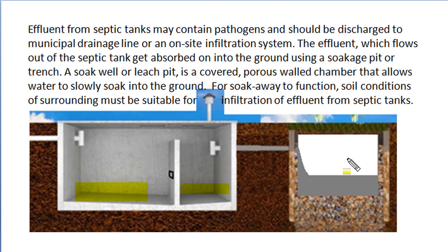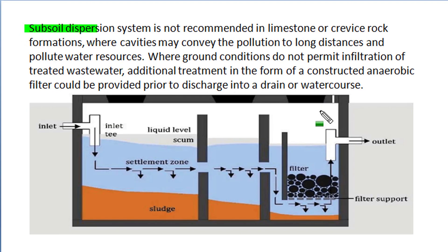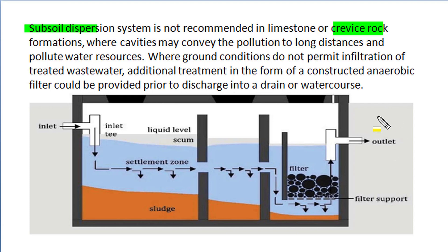The effluent which flows out of the septic tank gets absorbed into the ground using a soak pit or trench. This soak pit or leaching pit is a covered porous-wall chamber that allows water to slowly soak into the ground. For a good soak away to function, the soil conditions of the surrounding area must be suitable for infiltration of effluent from the septic tank. Subsoil dispersion or infiltration of effluent is not recommended in soil conditions which have limestone or cavernous rock formation, as the liquid effluent may create cavities that convey pollution over long distances and may pollute drinking water resources. Where ground conditions do not permit infiltration, additional treatment in the form of a constructed anaerobic filter could be provided prior to discharge into the nearby drainage system or water courses.